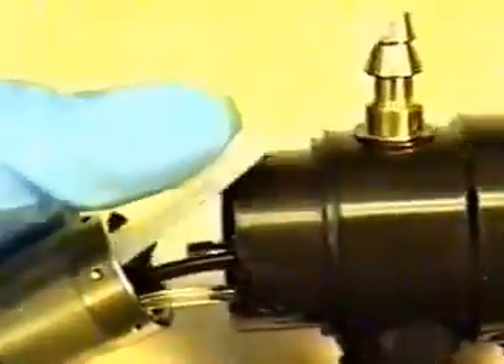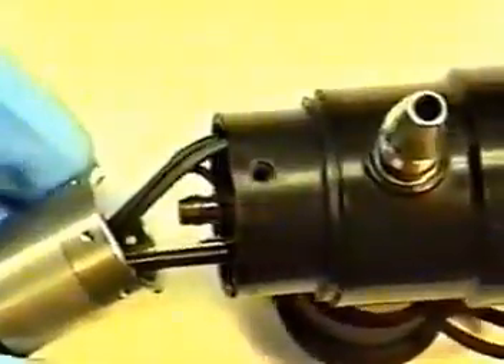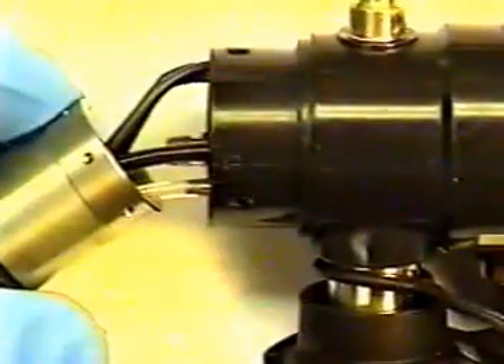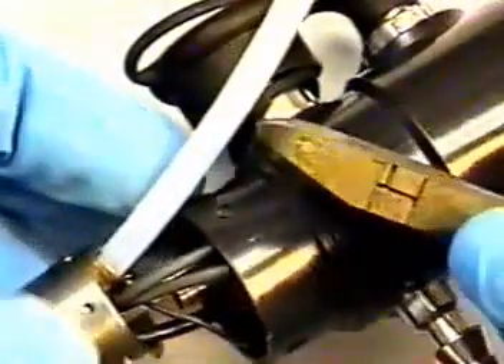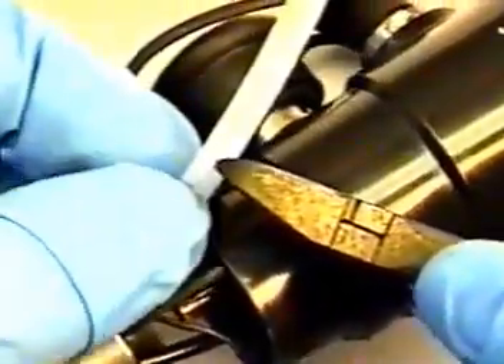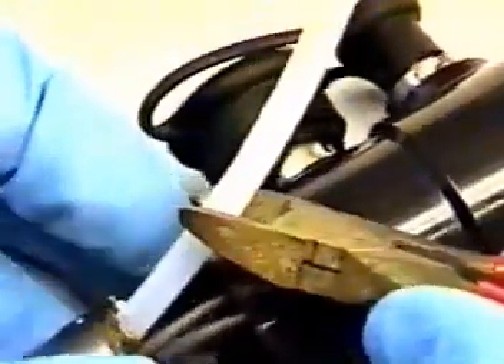We will now attach our suction channel to our suction channel port. Retrieve your suction channel clamp and slide it down over tubing. Using a very sharp pair of diagonal cutters, cut the SS suction tubing. You will make a cut which is approximately parallel to your suction port.